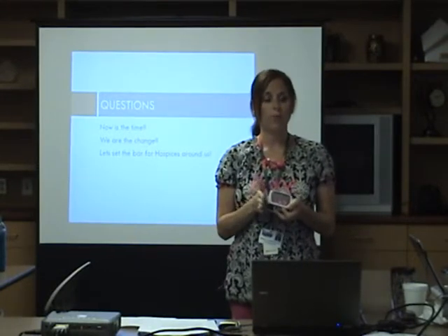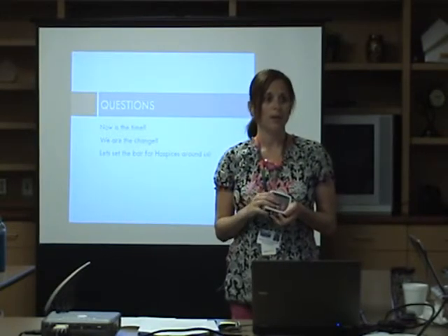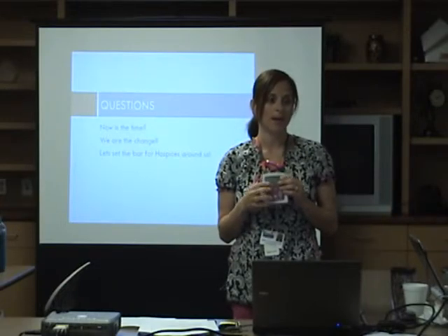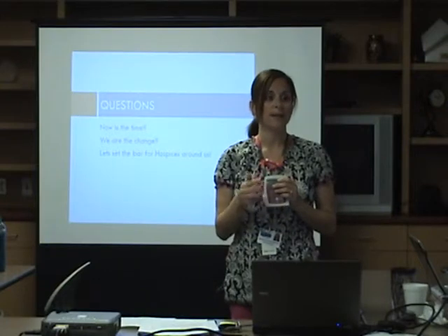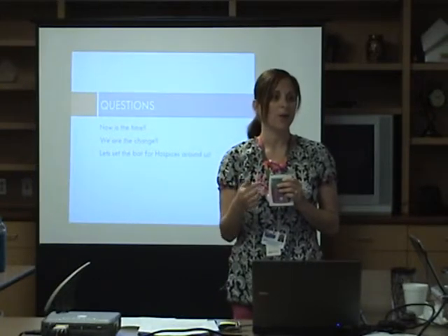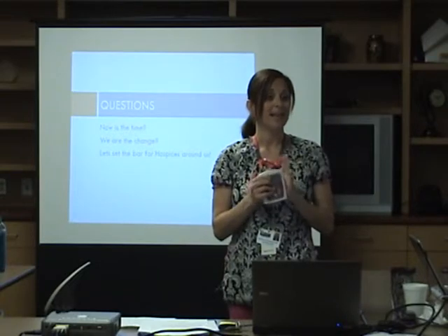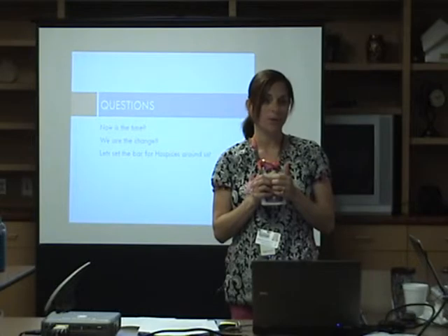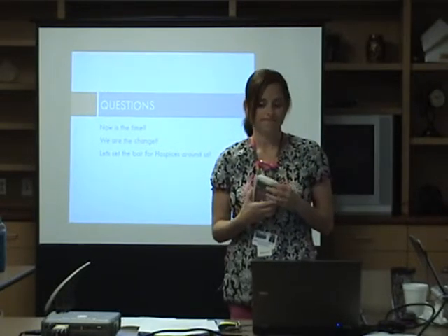So if we are doing our checks appropriately and keeping it on lock level 2, they can't change anything. So it really minimizes the risk of overdose. McIntyre in 2001 did a study as well. Granted, it was 2001, but he did a study that stated use our locks and don't share the codes with the families, and we will lessen our risk of overdose.